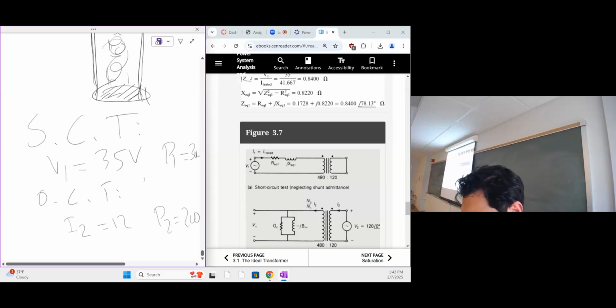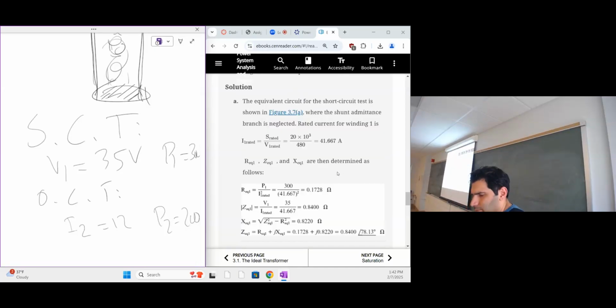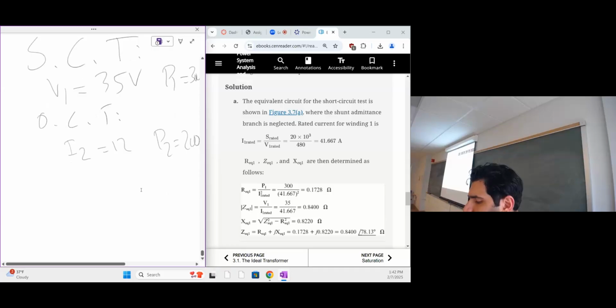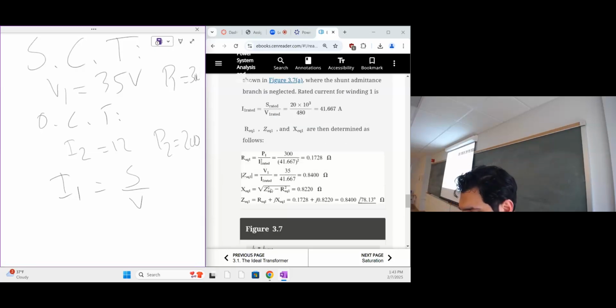So from the short circuit test, I have V1 and I have the P value. How can I proceed to get the values of R and X? Since I have the rated power of that component, I can get I, which is S divided by V. So you get the rated current for winding 1. This is the typical current that should be circulating if I'm using the transformer at its full capacity. And then I need to get R equivalent, which is P over I1 squared. I got the P value here, it's 300. And this one was calculated, it's 41.6, the rated current. So I would obtain R equivalent.